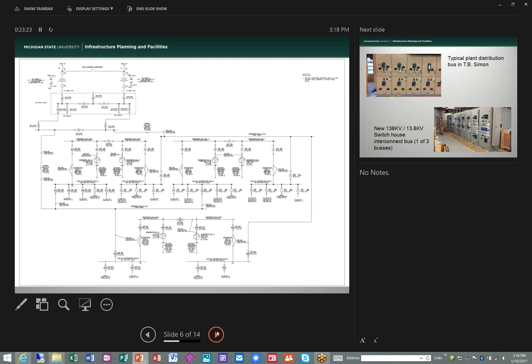So finally, with the FRIB, you're familiar with the FRIB project, quite a large electric load coming on campus with not much steam demand, no steam demand really. So the university decided to purchase that power for the FRIB. So we built the new substation. Consumers Energy built the new substation for us, still partially under construction. It shows a picture of it here. The substation's in the same footprint as the original one, so they built the bank on the left first, and we switched over to the new sub, and then they tore out the old substation on the right, and now they're in the process of building the second bank there. There's room in the middle, and all the foundations are going to be in place for a third bank in the future.